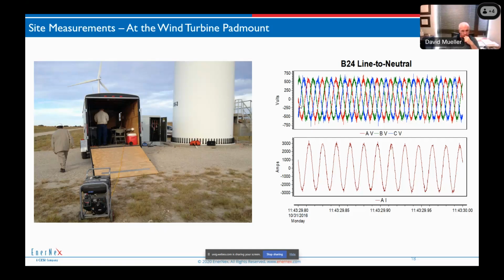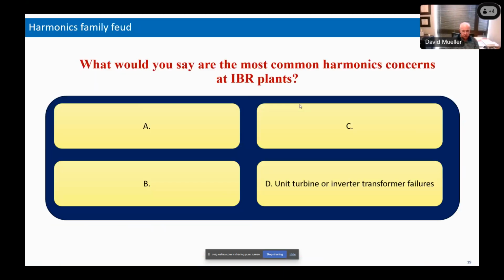Sometimes it's been found that there was a problem in manufacturing, where there wasn't a clearance, say, around the tap change mechanism or something like that. So it's not always harmonics, but certainly harmonics get blamed for it. And so I have to include it in my list of harmonic problems, these transformer failures.